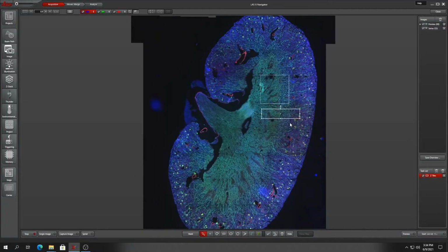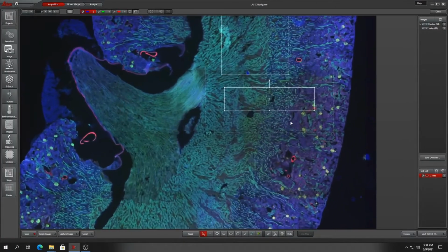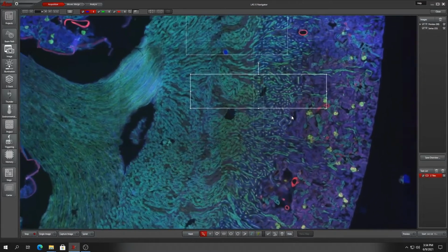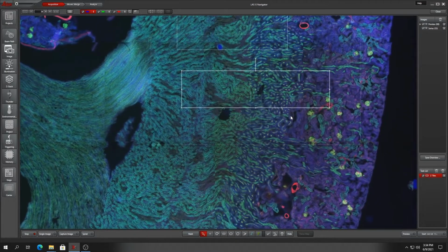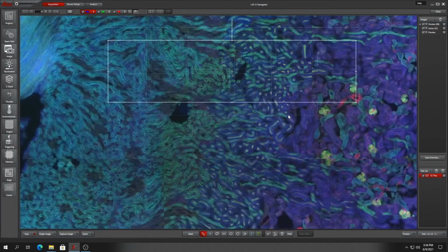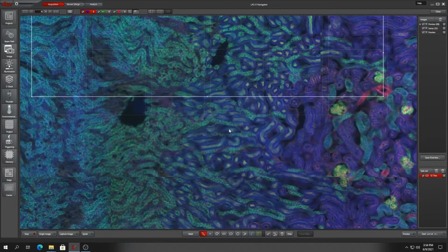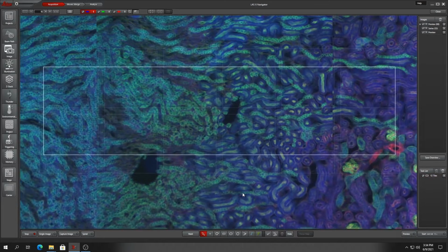For applications where a 3D image of the sample is important, you may want to add a Z-stack with higher resolution. Adding it in LASX Navigator is easy. Select a region of interest and switch to an objective with higher magnification. The LASX Navigator will automatically plan the tiles for the higher res scan.